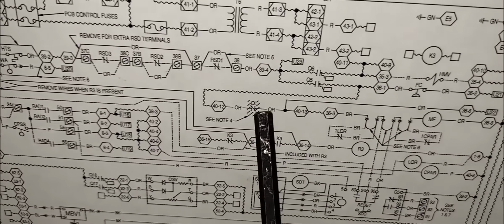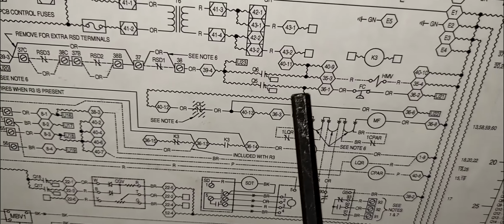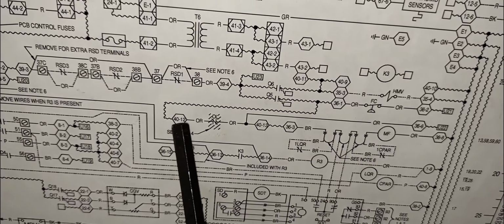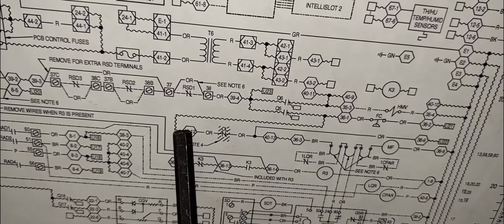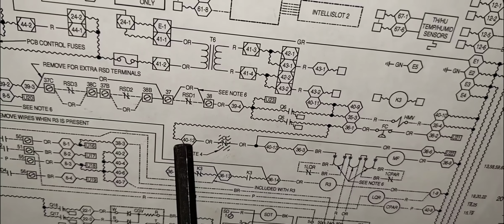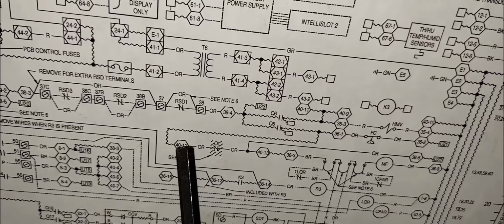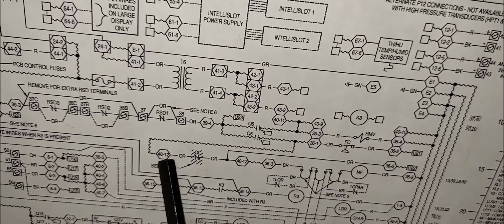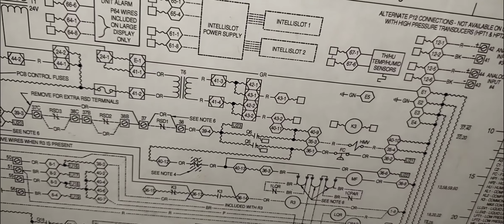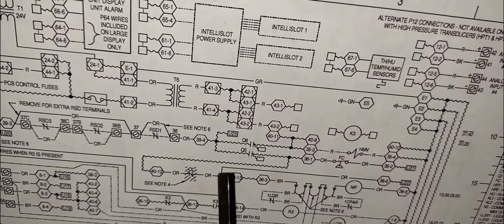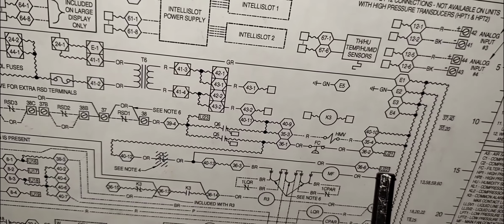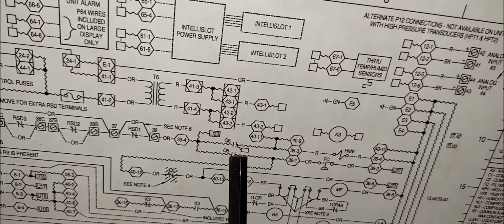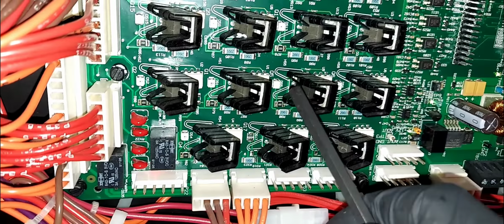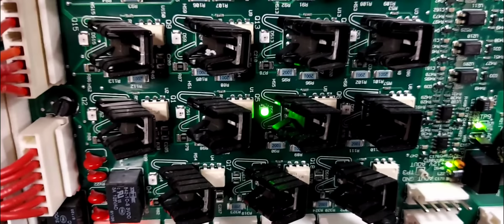Right? Again, 24 volts is right here. Clearly we know this. And I could check with my meter on the board at this connector. Connector 40 and wire number 12. I could check. Usually these things are really good with the indications, so I trust it. So here is where we have the alarm, because this input is not seeing 24 volts while this triac is closed. Okay, so that's Q5 is closed, and so that's why we're getting the alarm.